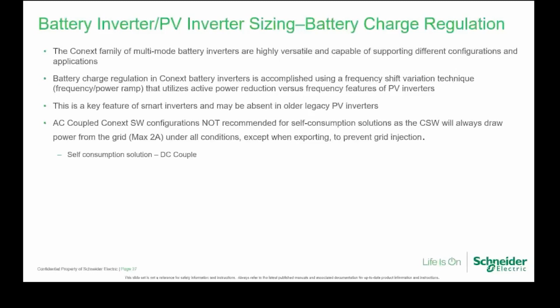Another thing is the AC-coupled Conext SW configuration is not recommended for self-consumption, as this SW will always draw power from the grid, a maximum of 2 amps, under all conditions except when exporting, obviously. That sort of prevents the grid injection, because the SW cannot export out. But remember that when you do AC coupling, it will export out. So you can't do a solar self-consumption solution. The only way you can do self-consumption with the SW is to do a DC couple.